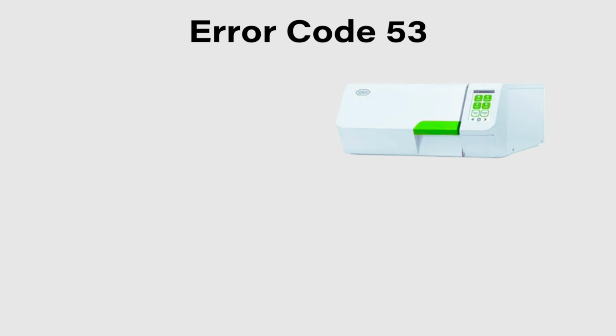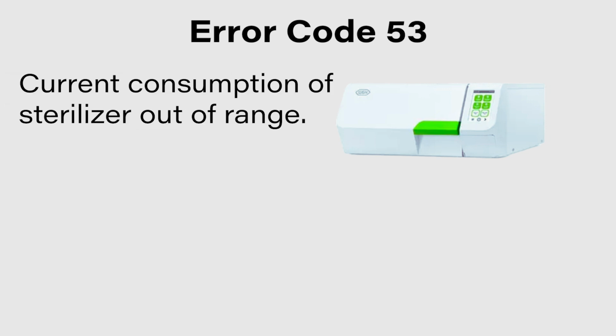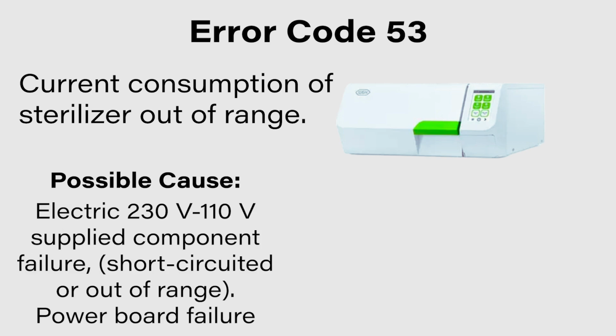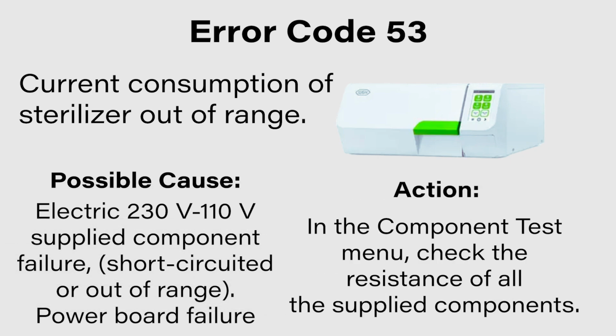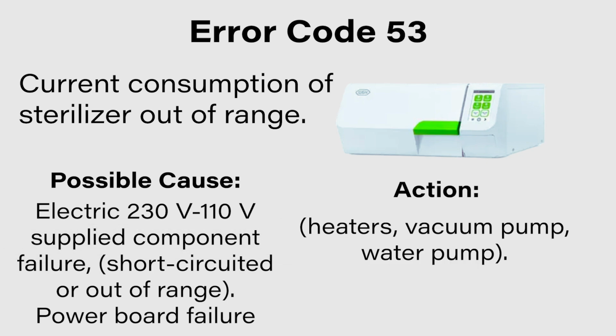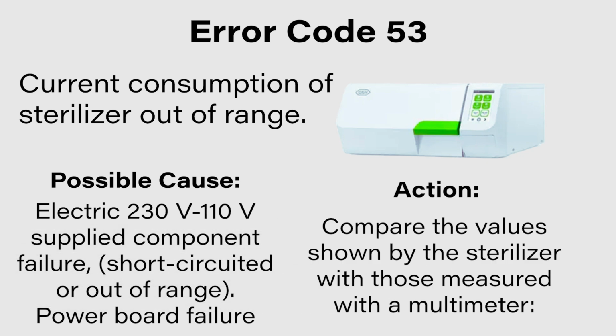If your W&H Lexa Mini is displaying an error code 53, that means that the current consumption of the sterilizer is out of the range. The possible cause is an electric 230 volt or 110 volt supplied component failure, either short-circuited or out of range, or a power board failure. For this, in the component test menu, check the resistance of all the supplied components, the heaters, vacuum pump, and water pump. Compare the values shown by the sterilizer with those measured with a multimeter.